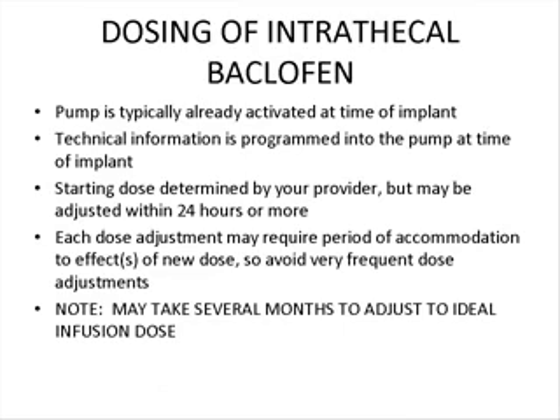So what about dosing of intrathecal baclofen? There's a lot of technical information that's programmed into the pump at the time of implant, in addition to the pump infusion starting in the majority of cases. The starting dose is determined by your providers, and this dose may be adjusted within the first 24 hours or more. The only caution I would have with too frequent of a dose adjustment, because it really can be done almost every day, is that you need a period of accommodation in terms of what your functional skills are to the new dose. And if you're rapidly changing that, your body's trying to get caught up with what the functional abilities are as they change. And so I would leave a little period of time where you need a little bit more accommodation.